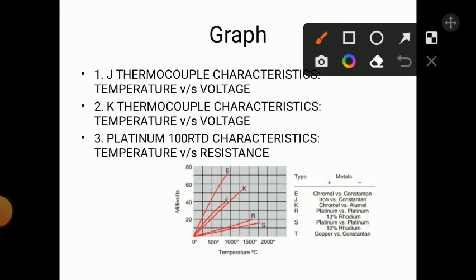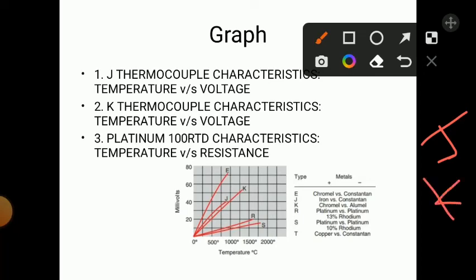Looking at the thermocouple types table: E type uses chromel and constantan; J type uses iron and constantan; K type uses chromel and alumel. Other types include R (platinum vs. platinum + 13% rhodium), S (platinum vs. platinum + 10% rhodium), and T (copper vs. constantan). In this experiment we use J and K type thermocouples.